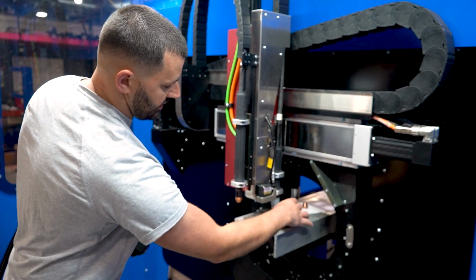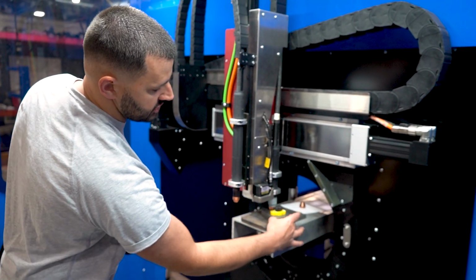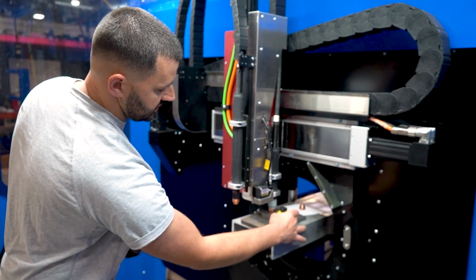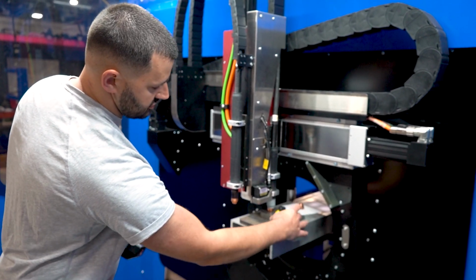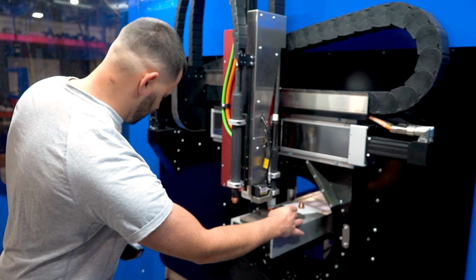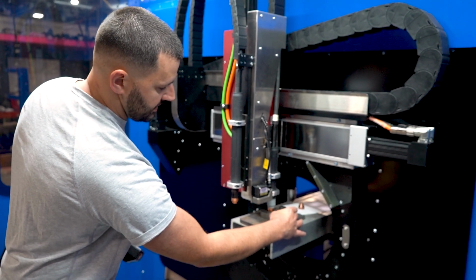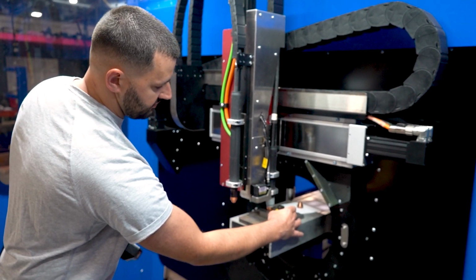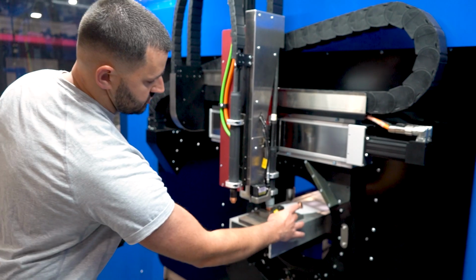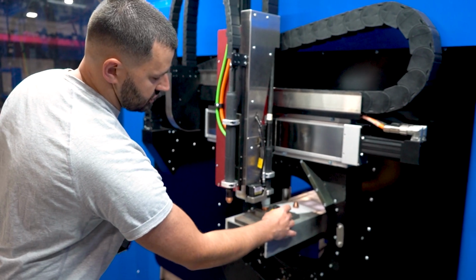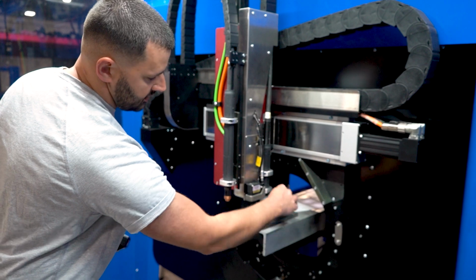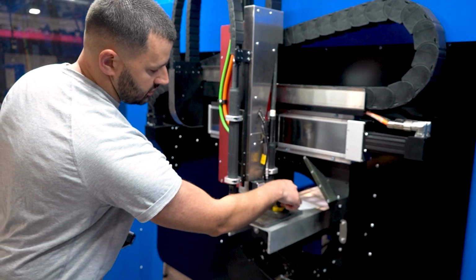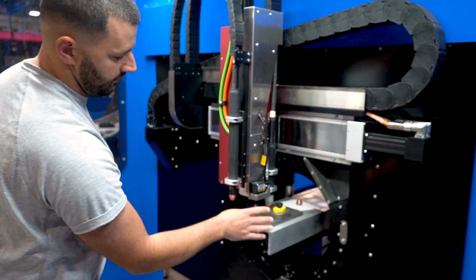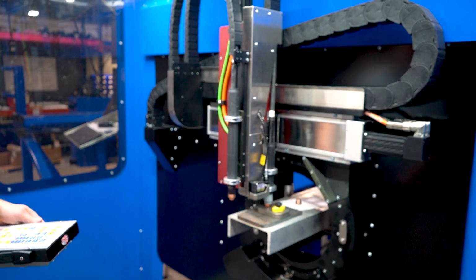So you can see right now you can just float the calibration tool very lightly. You don't want to influence the torch, so you just want to very lightly rotate it around. And you're going to increment it down until you just feel it touching. So once you just start to feel friction, you can go one more and it'll kind of stop it then. We're going to go ahead and turn the magnet on. Try to be light and not altering the position of the torch.